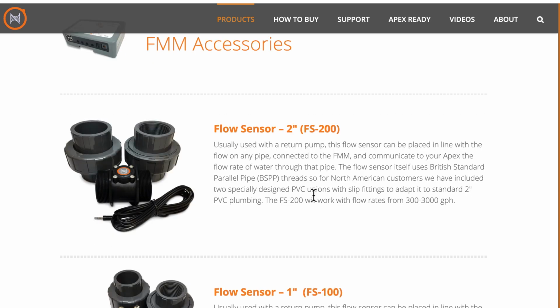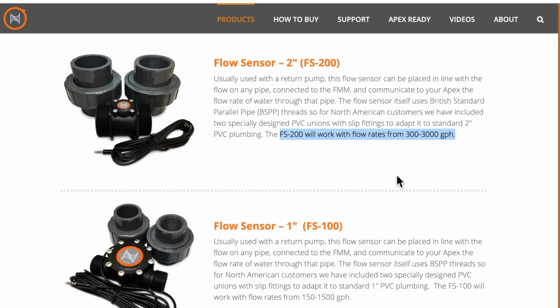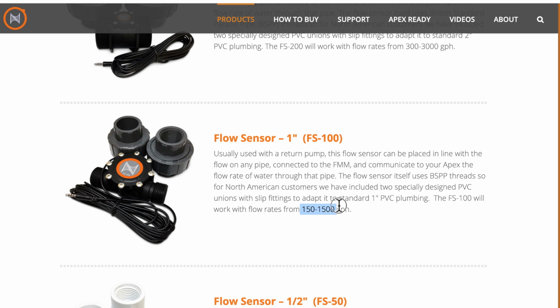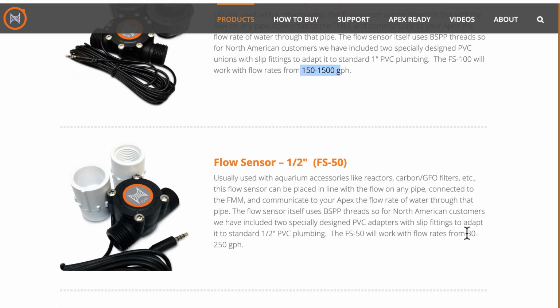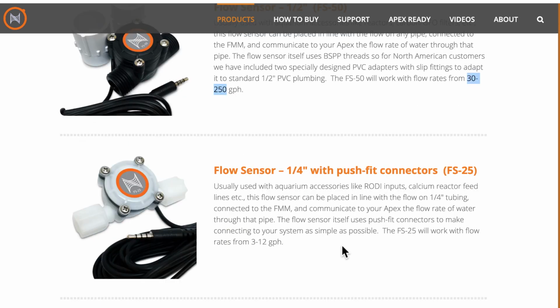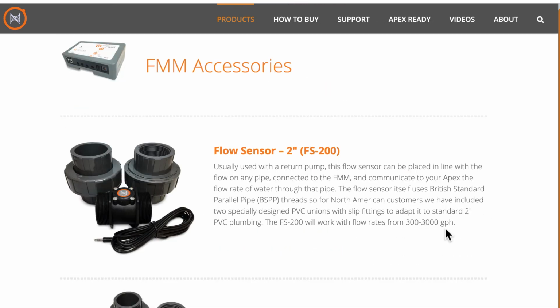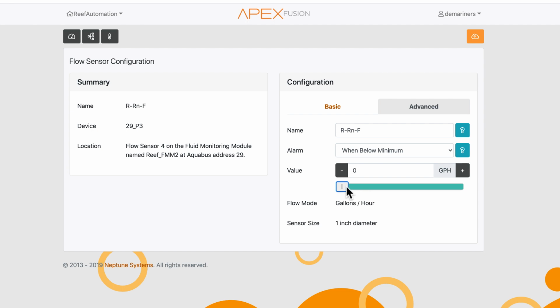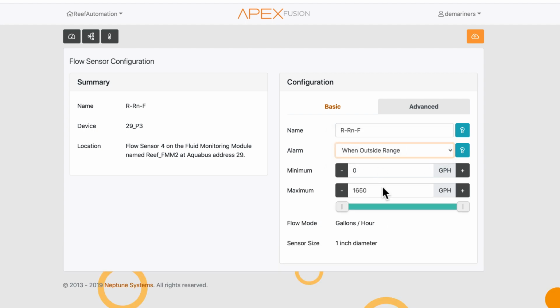Now again, you will see that the FS200 will only work between 300 and 3,000 gallons per hour. So if indeed you have a flow that's lower than 300 or higher than 3,000, this is not going to work for you. The FS100 will work from 150 to 1500. The FS50 will work from 30 to 250. And then your 1/4 inch, which is the smallest one, the FS25, will only work between 3 and 12 gallons per hour. So again, if your flow rate does not go in between this flow, you will not see it on your flow sensor. So again, my 1-inch diameter, if I want to get an alert below maximum or outside, I can set it right here, and then it will give me alert.